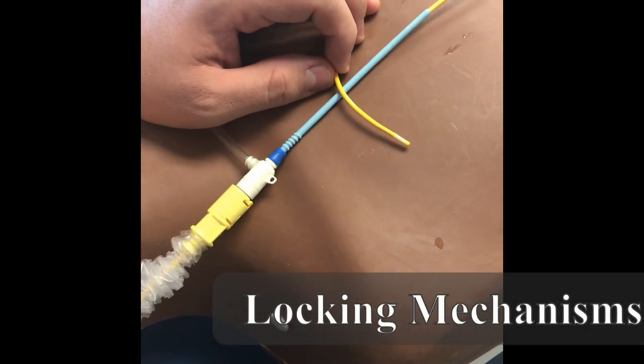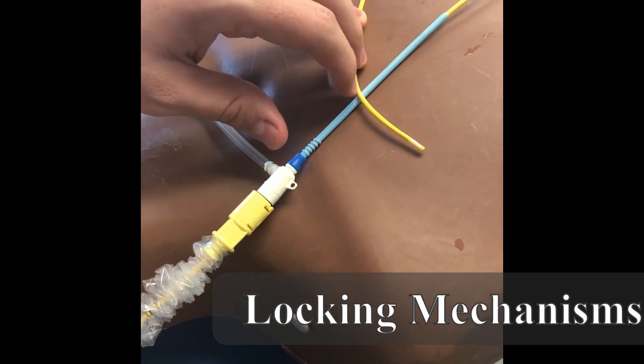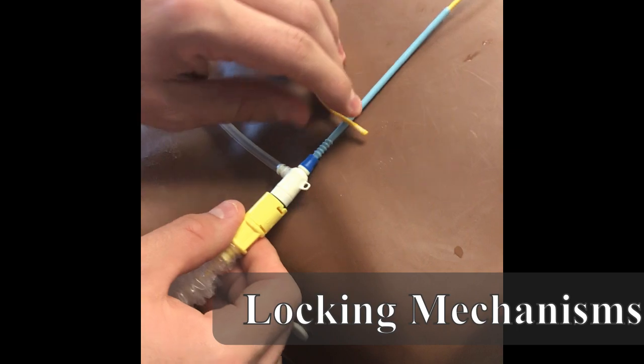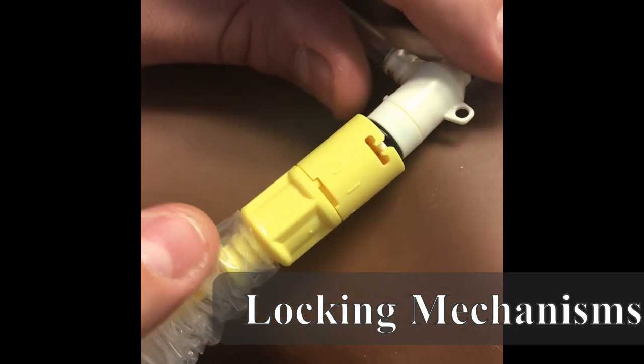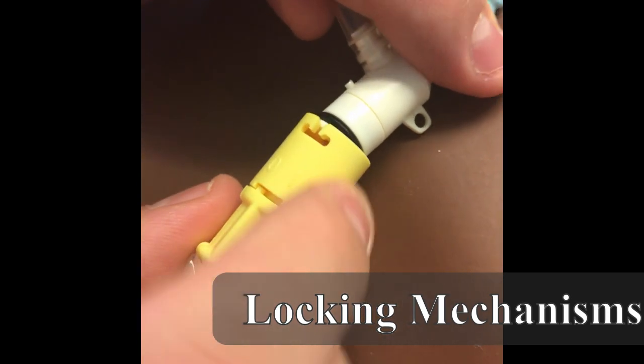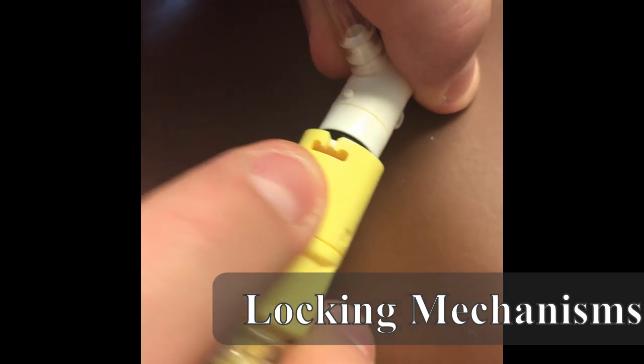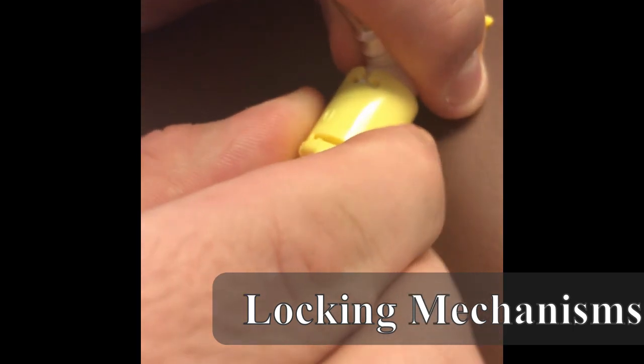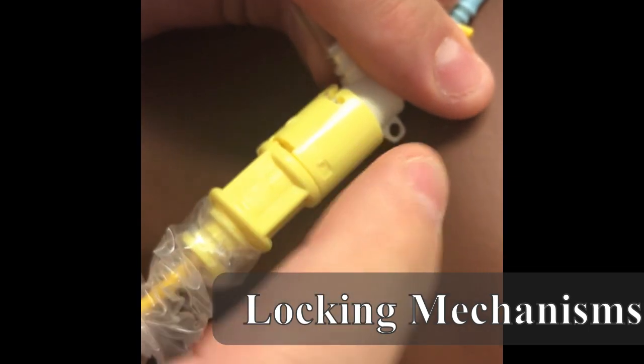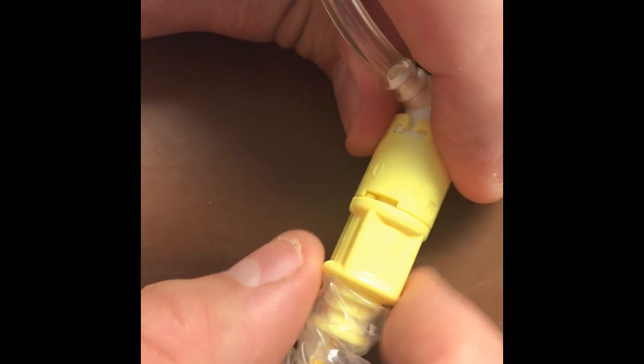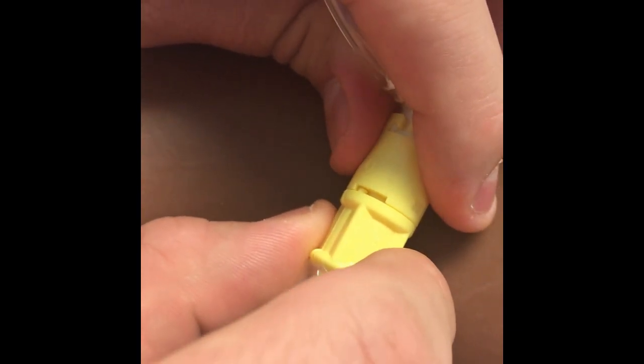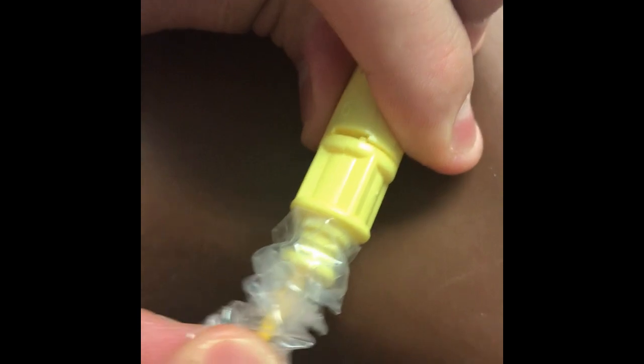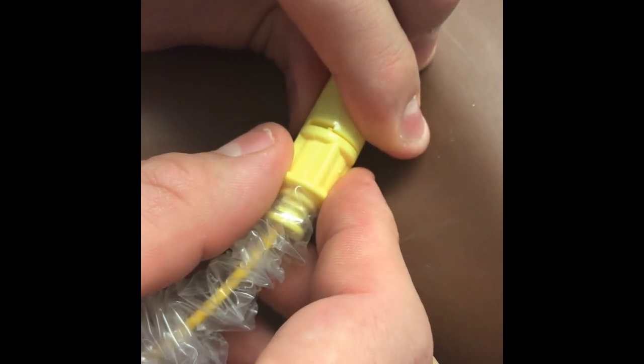After you have inserted the right heart catheter or the Swan-Ganz catheter and you're happy with your position, look over this cover and you can see that there's an area over here that has a notch, and you can actually put this notch through and then you can turn it a little bit. That will make sure that this tip is connected to the sheath. But there is also another locking mechanism, and you can see that here there's number 1 and number 0. Number 0 means it's free, but when you rotate it clockwise to number 1, basically this puts tension on the catheter so that it doesn't move.